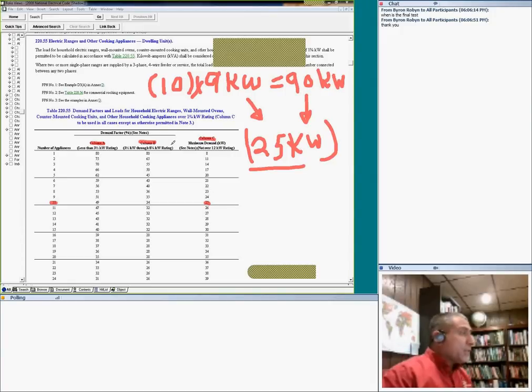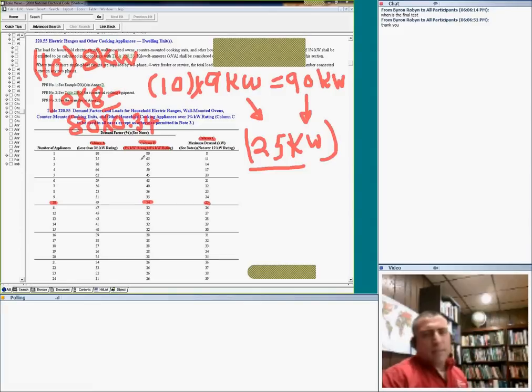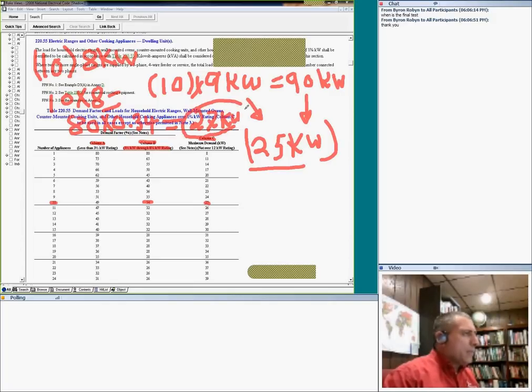Again, the range has a different calculation. Suppose we have another 10 ranges, and these are 8 kW each, guys. These 10 apartments, my 10 at 8 kW, are under here, and then I have to cut them by 35%. So you take the 10, multiply by 8, that gets you 80, and then multiply by 0.34. Your demand, you cut by 0.34. If you do the math, 80 times 0.34 equals 27. So that gets you 27 kW demand. So when I size my feeder or service, depending on how the system is laid out, I only account for 27 kW.